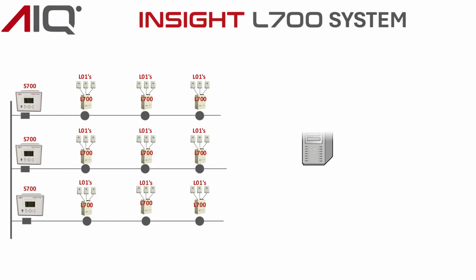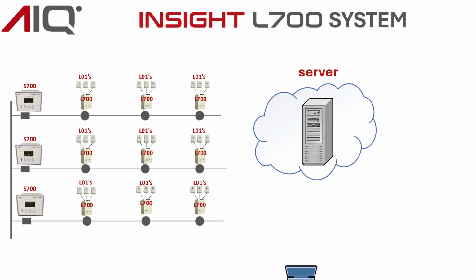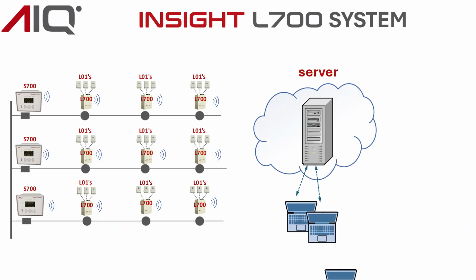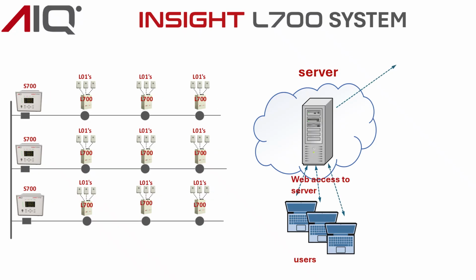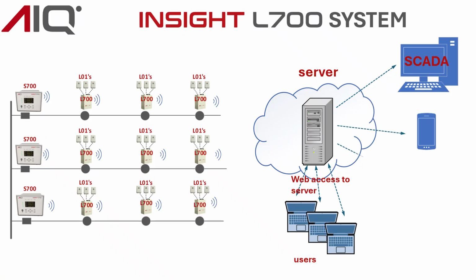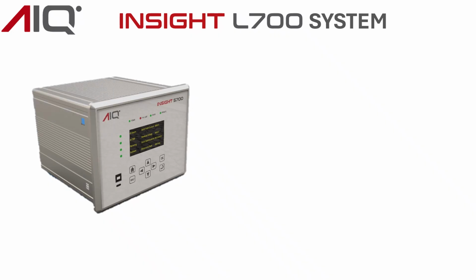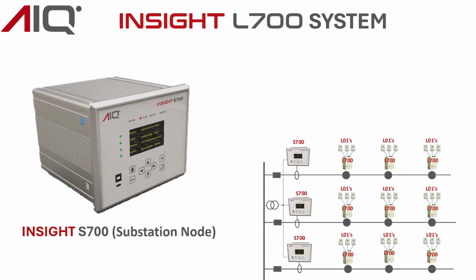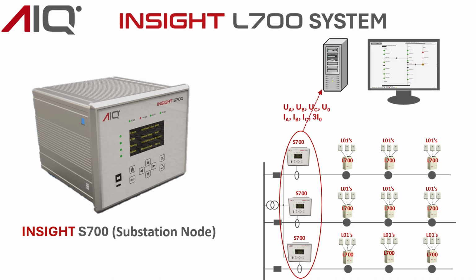All deployed devices communicate via 4G, 5G to a dedicated secure server that hosts the master system software. Within seconds, fault activity is communicated to operators via SCADA, smartphone, and email, detailing the fault in terms of what, when, and where it was. For security, the data is end-to-end encrypted. For equipment deployment, an S700 is installed for each individual feeder in the substation, with current inputs via clip-on CTs. In addition to fault location, the high sensitivity of the S700 supports protection.